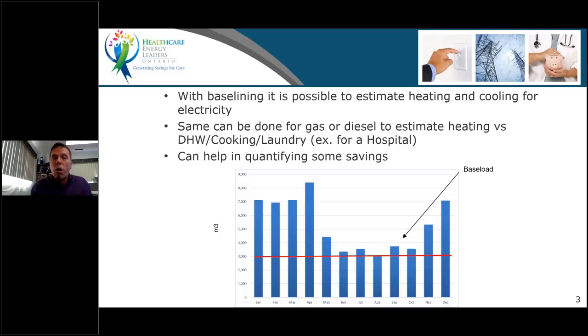In this case, for example, this specific hospital, they thought that their heating was by far their largest gas usage, and it was not. The percentage for heating, and I did not put the answer there, is 35%. 65% of their gas was used, and like I said, I want to say it's an estimate, but it is probably the better estimate you can get, other than trying to do a lot of calculation manually, all of which are filled with uncertainties. So 65% in this case was base load.